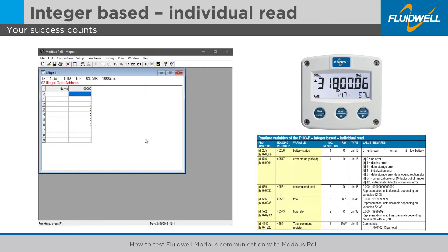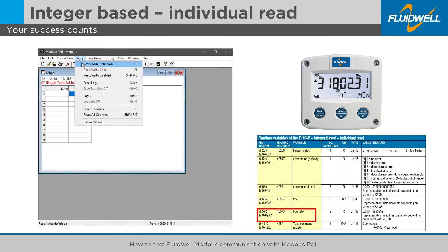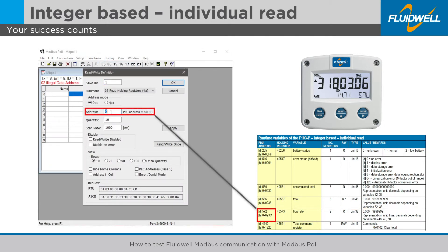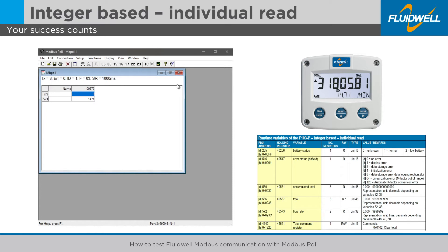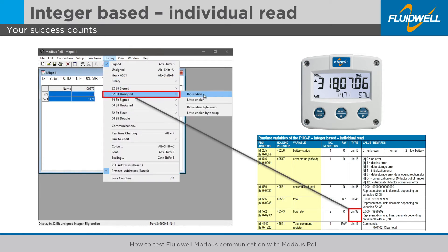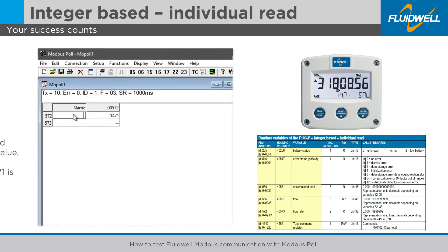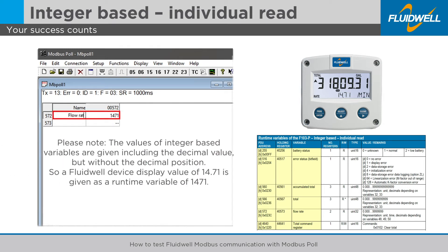Let's take a look at how this works. For an integer-based individual read of the flow rate, select the corresponding table in the manual. The table shows the PDU address of 572 and the number of registers, which is 2. Apply the 32-bit unsigned integer data type with Big Endian register order to the received data for a correct reading. Please note, the values of integer-based variables are given including the decimal value, but without the decimal position.